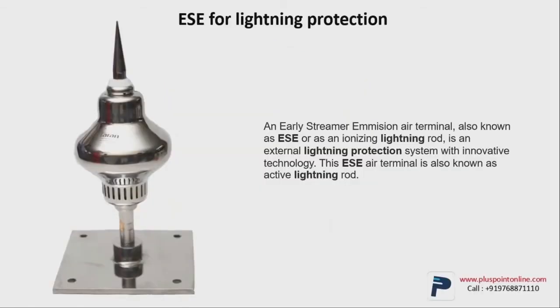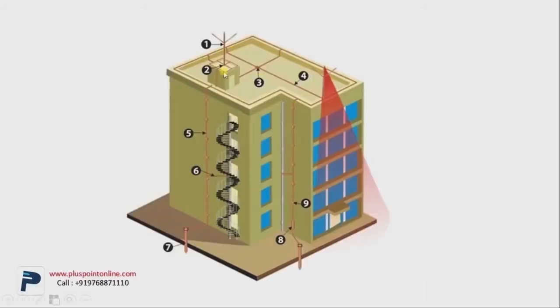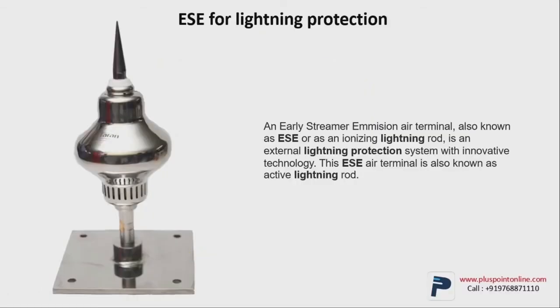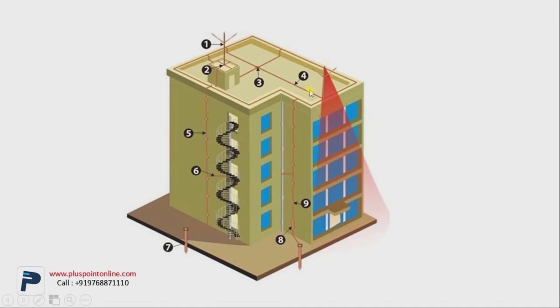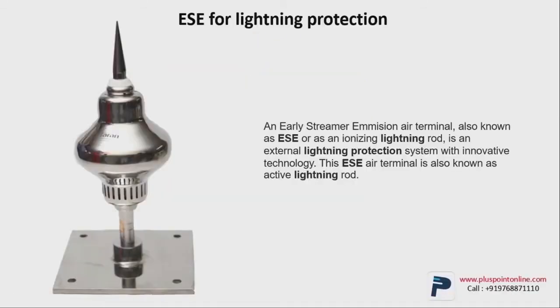The latest technology is the ESE lightning protection system. ESE is also known as an ionizing lightning rod and an active lightning rod. The lightning protection system is developed as per modern technology. You must have seen in this system that the copper rod has been set up on the top with the copper strip attached to the ground. As you can see, there are multiple copper rods attached on the roof of the building. But with this modern and innovative technology, just one rod can complete the work. There's a small circuit in the rod. One part of it is facing the ground and the other is facing the top. As the weather gets worse, it gets charged, and once the lightning strikes, it gets discharged and transfers the entire energy into the ground. Let me explain this with the help of animation.